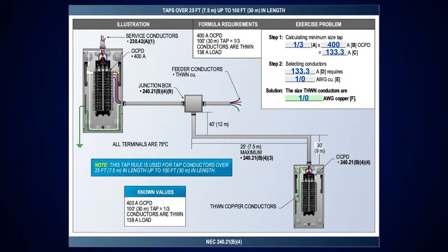So I'll go to table 310.16, 75 degrees C column. The next size above the 133.3 is 150. Come across, it's going to tell you that the size THWN copper conductors are required to be 1/0 AWG. Simple. And if you notice, I didn't change anything. I stayed the same process all the way through.